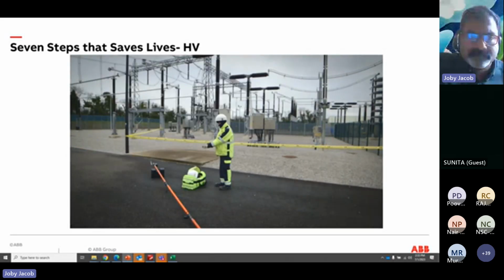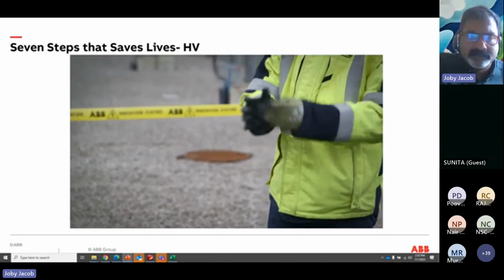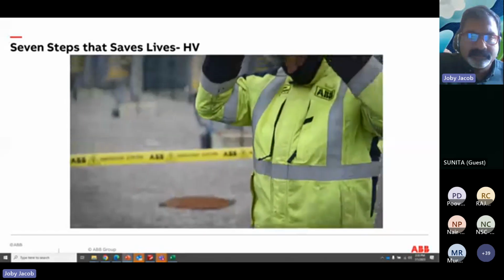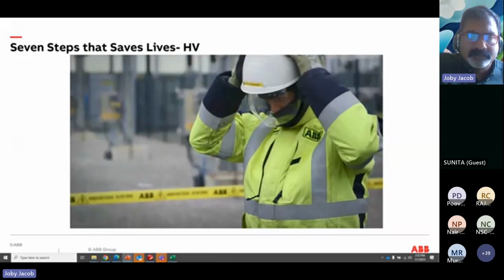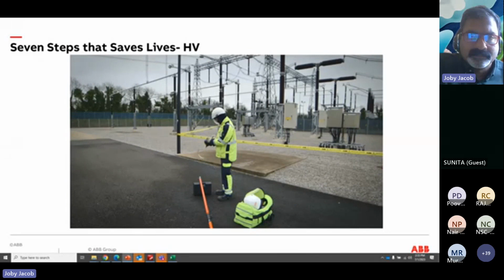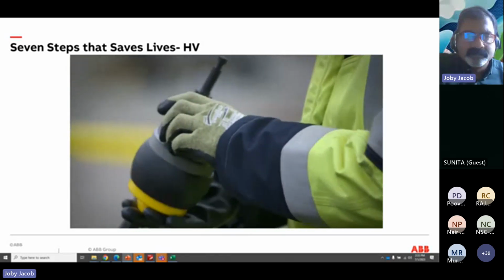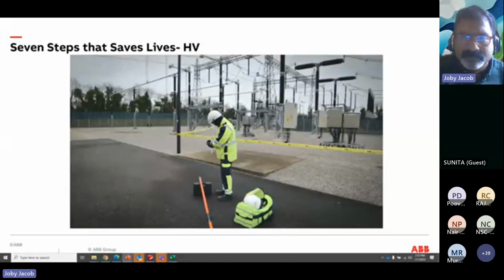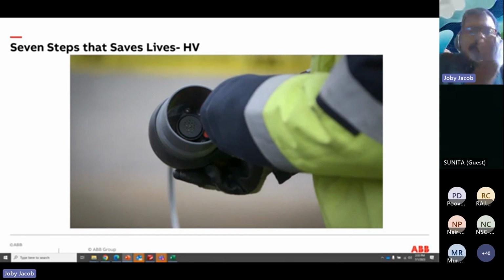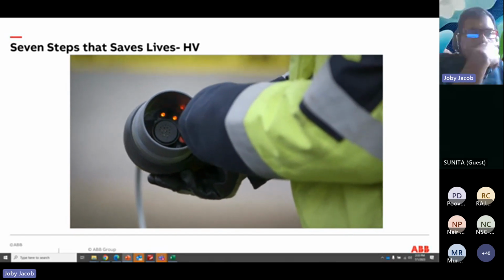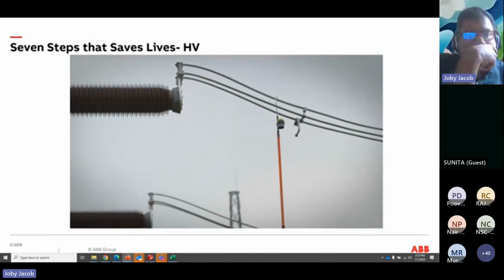Utilize only properly rated and calibrated voltage detection devices and wear the proper PPE identified in Step 1. It is extremely important that you test the voltage detection device on a known live source or by using the detector's test button if designed into the device, then test for the absence of voltage.